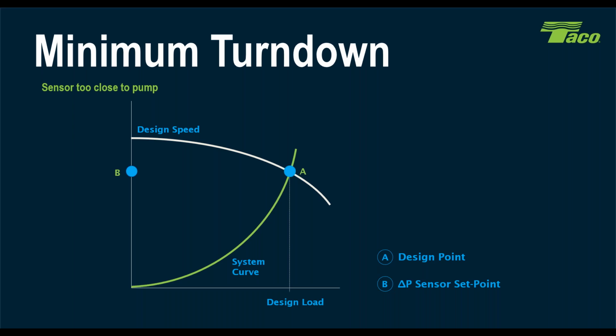So if I put it in the mechanical room, and I look at my design point, my control curve is going to flatten out, because I'm going to get very little change in differential pressure in the mechanical room where the pump is, compared to the set point I need out in the system.